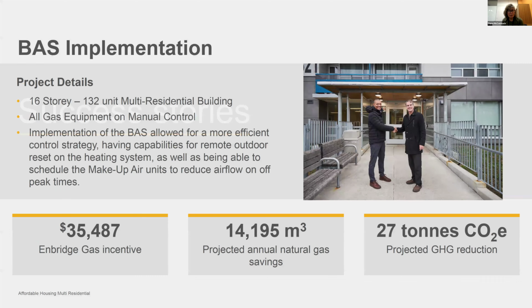I do have just a couple of implementation stories to tell. So this is just a control job where they implemented a BAS system. The boilers had been running off of their limits. And they also included the makeup air units. They received $35,000, saved 14,195 cubic meters per year, which is perpetual savings beyond just the incentive, which I think is the biggest benefit of any of these projects, that you're saving continuously year after year. And they also reduced their carbon footprint, which is something we're all striving to do as well.